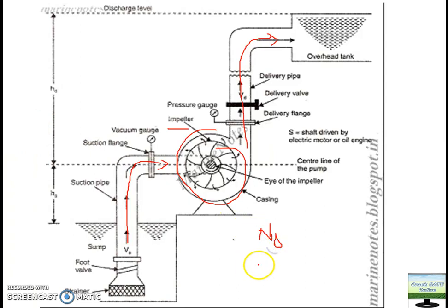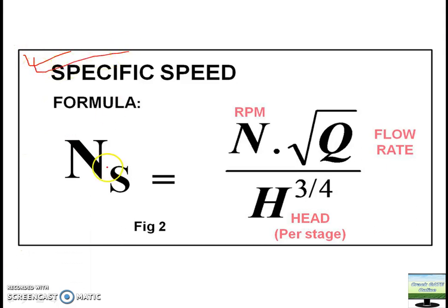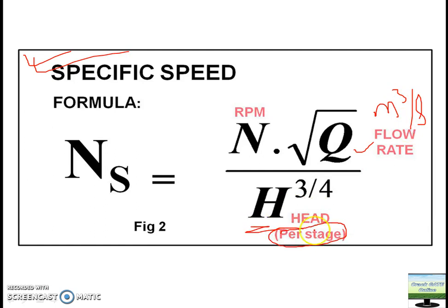In the centrifugal pump you need to understand two concepts: first is the concept of specific speed, and second is the affinity law. For specific speed, remember this formula: Ns = N√Q / H^(3/4), where Q is the flow rate in cubic meters per second, H is the head per stage in meters, and N is the RPM of the pump.